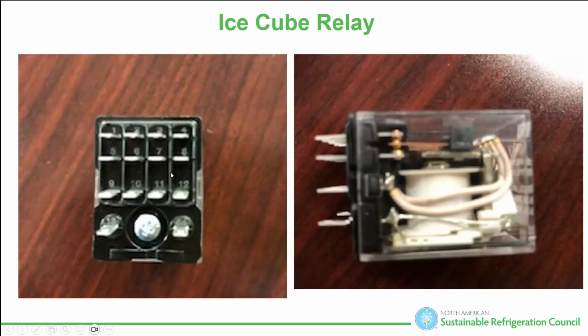I can wire this one normally closed, so I energize the coil. I can turn this on and this off. So when you're troubleshooting and thinking about relays, understand it's not a single function, it doesn't have to be a single function. And remember, the voltage here, maybe 208, maybe 24 volts DC, maybe 24 volts AC.